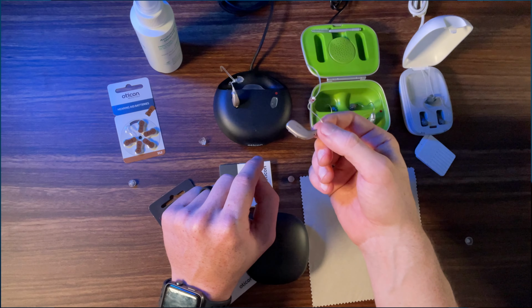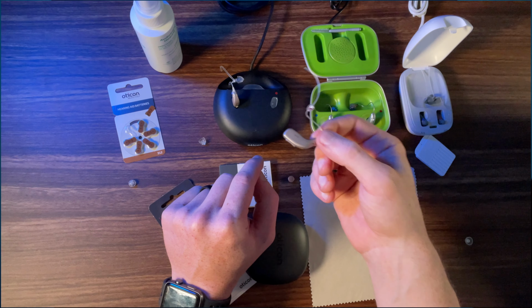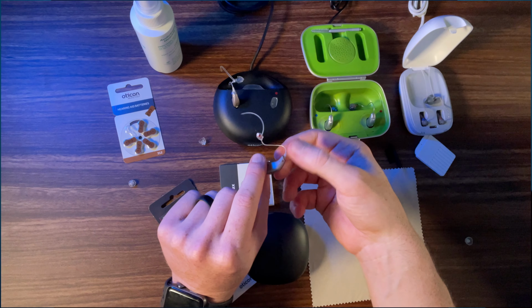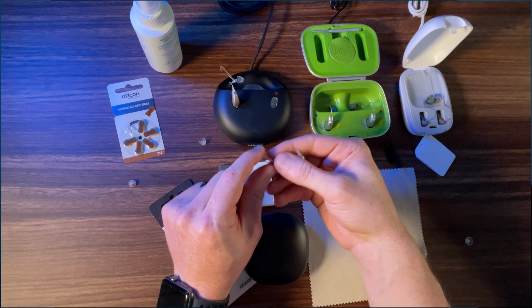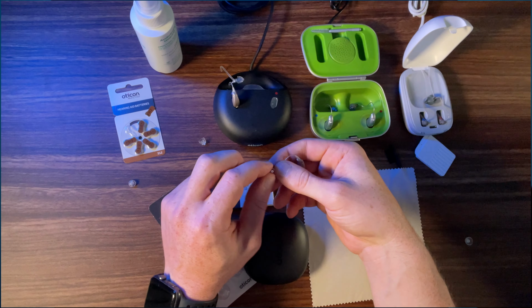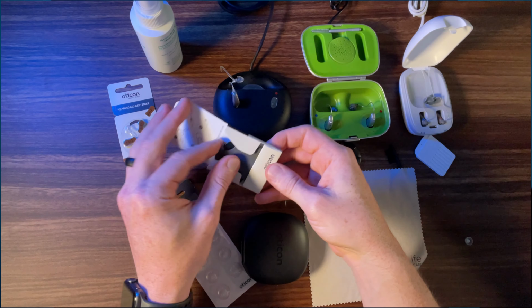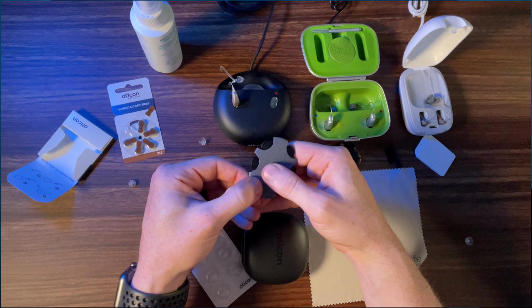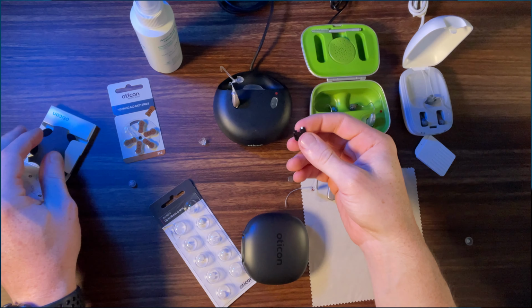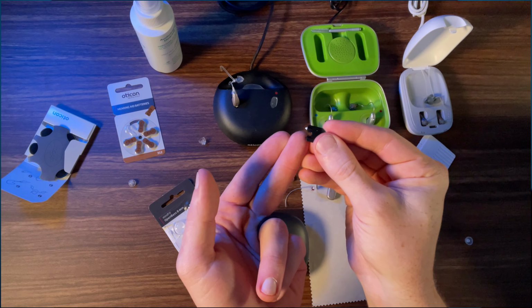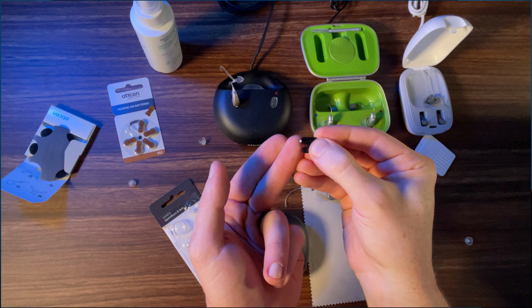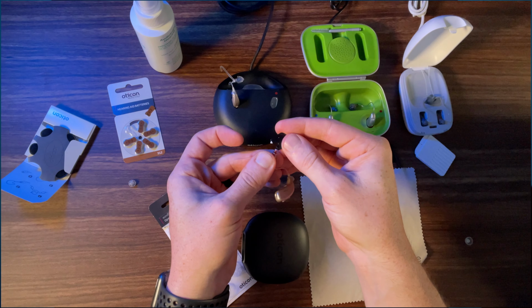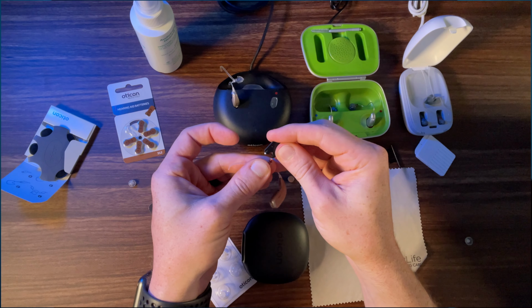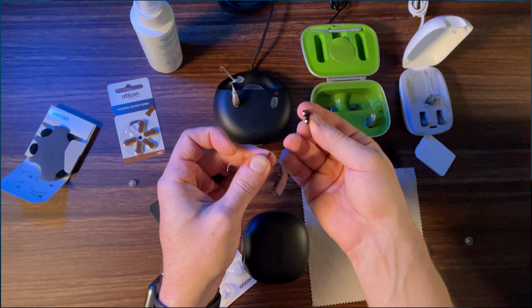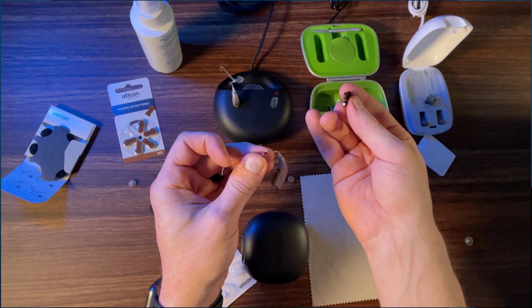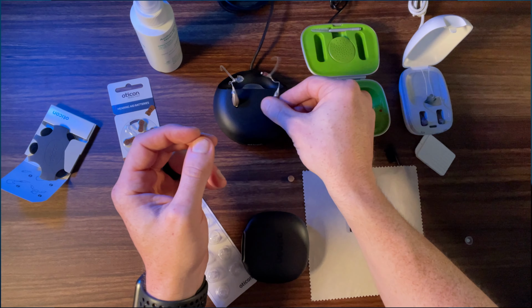So replacing your wax guard is actually the number one recommended troubleshooting tactic if your device ever stops working. If you're ever not hearing out of your hearing aid, the first thing we recommend is to replace the wax guard. The way that you're going to do that is you're going to take the manufacturer's wax guard tool. You're going to pull one of them out in this case, and you can see with the Oticon wax guards, this is a removal tool, and that's a replacement wax guard. So we're going to stick the removal tool straight into the receiver opening of the hearing aid, pull the old one out, and put a replacement in. So that's fairly straightforward. And then this guy is trash, those are disposable.